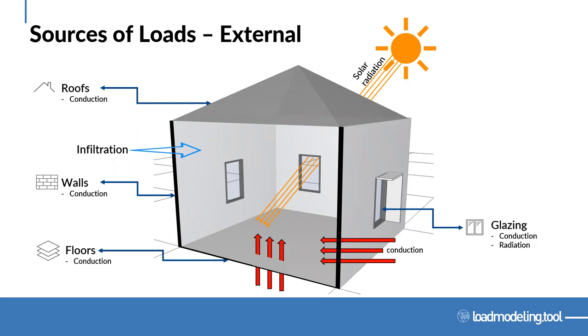Solar radiation comes in through our windows and adds heat to the building based on window size and performance — specifically the solar heat gain coefficient, which determines how much solar radiation is blocked by the glass itself, reducing some of that load. Other means to reduce load might be shade devices, whereas the properties of the glass itself can also reduce some of that solar radiation.